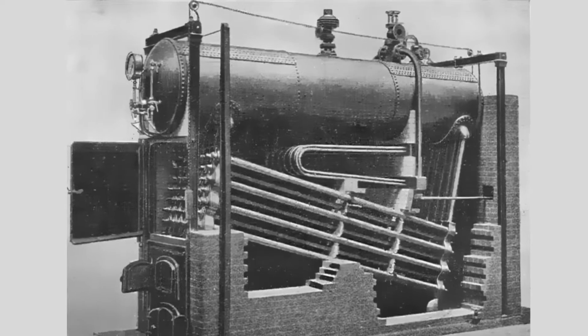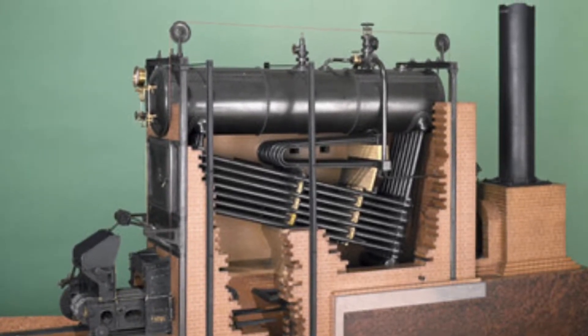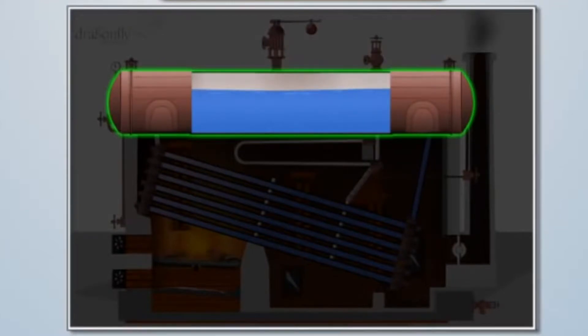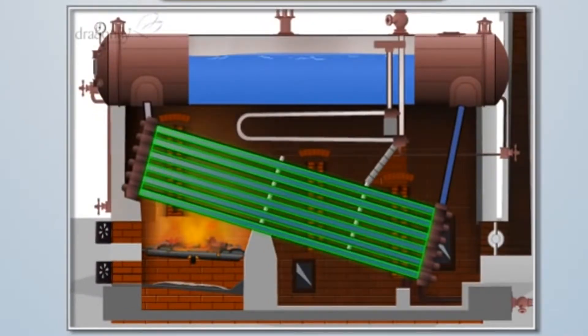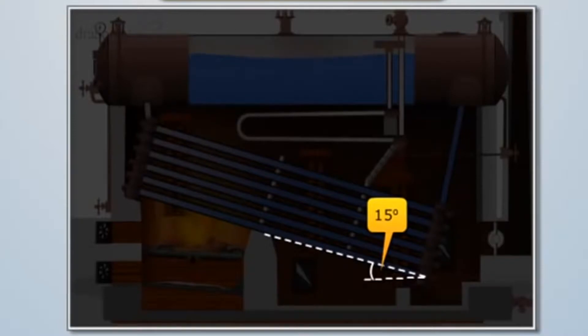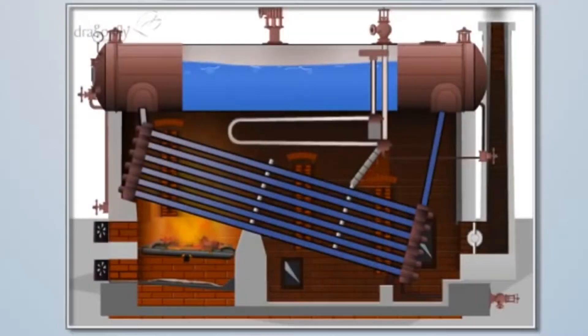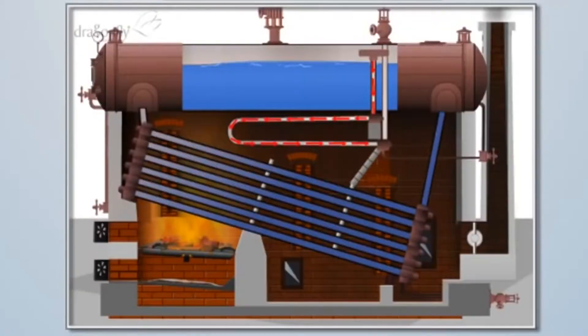Babcock and Wilcox Boiler: Developed and patented in the mid-19th century after the Babcock firm acquired the Wilcox boiler design, this boiler has only one tank — the steam drum positioned at the top, partly filled with water and partly containing saturated steam. A typical feature is water pipes designed to be tilted 15 degrees to ensure natural circulation of water and steam. On top of the inclined pipes is a superheater tube section where saturated steam from the steam drum is further heated to superheated quality. The flow of combustion gases is made tortuous to maximize heat absorption from flue gas to the water-steam mixture.